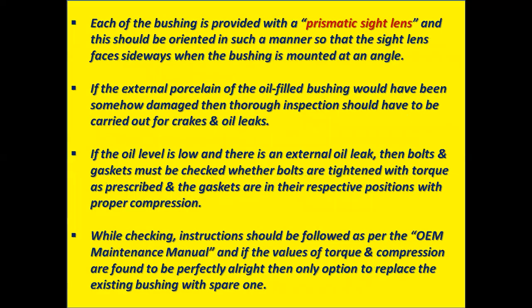Each bushing is provided with a prismatic sight lens, and this should be oriented in such a manner that the sight lens faces sideways when the bushing is mounted at an angle. If the external porcelain of the oil-filled bushing has been somehow damaged, then a thorough inspection should be carried out for cracks and oil leaks.